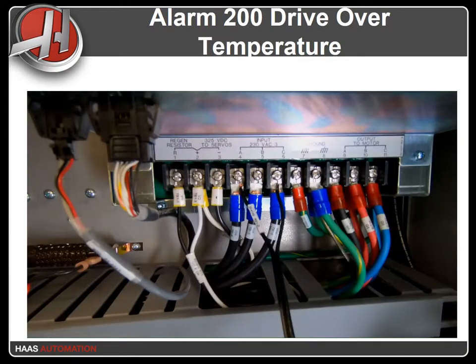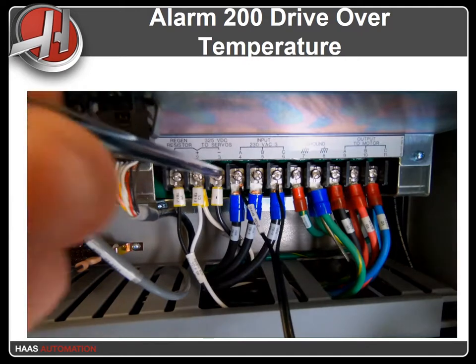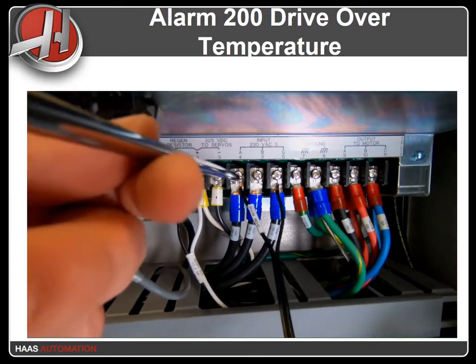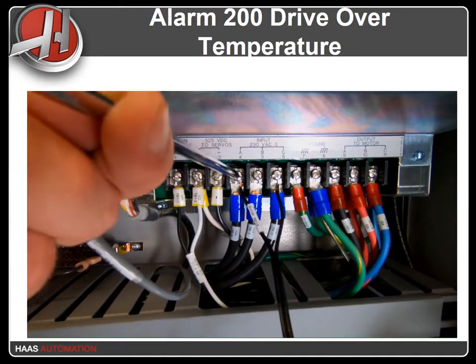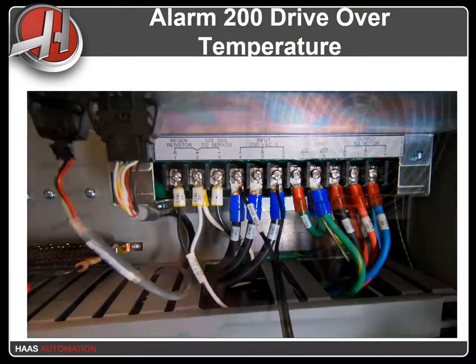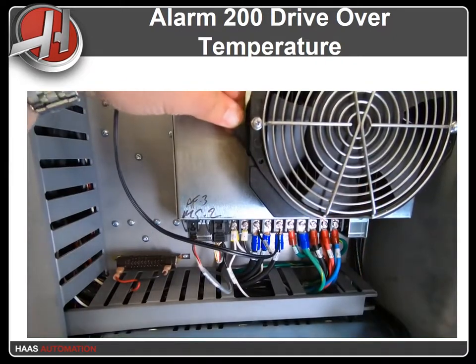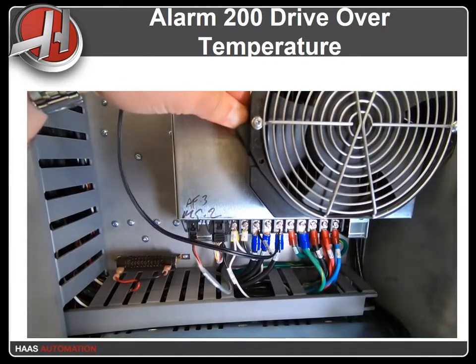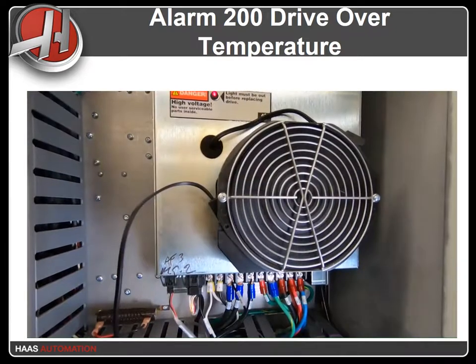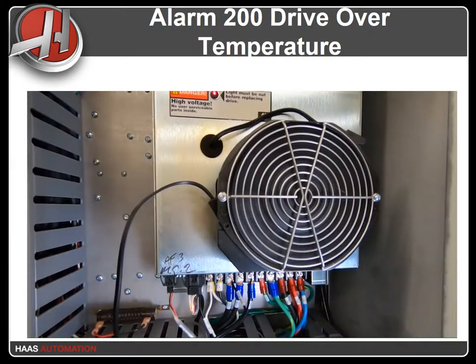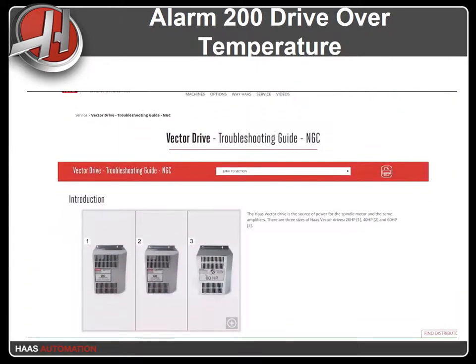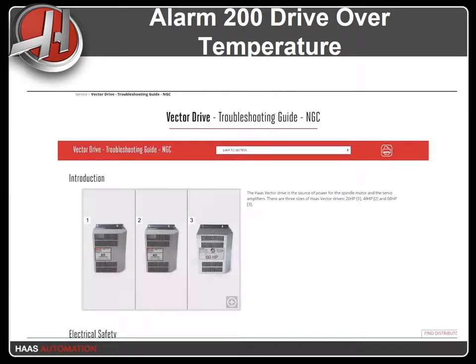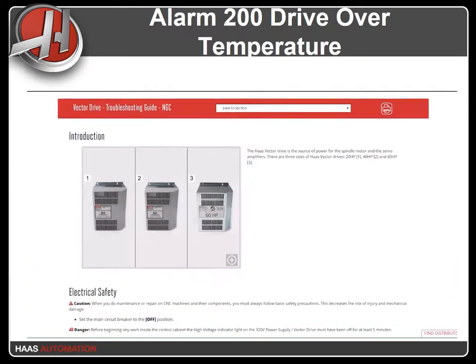If you do not have a spare fan, another method to check the fan is to connect the fan directly to the Vector Drive. Using a spare fan cable, connect the leads to the 240 volt AC input supply voltage A and C terminals. Turn on the machine. If the fan turns on immediately and at a normal speed, then the Vector Drive is faulty. For more information on troubleshooting the Vector Drive, refer to the troubleshooting guide on our website.